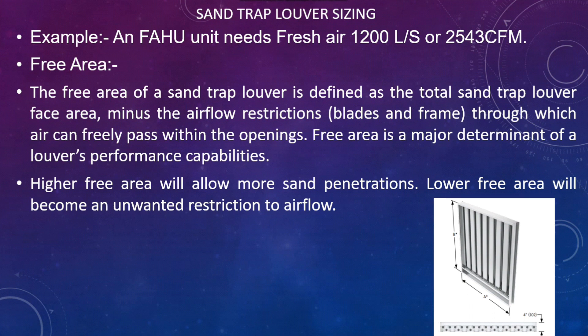The first important thing here is the free area. The free area of the sand trap louver is defined as the total sand trap louver face area — that is A times B as shown in the drawing — minus the blades and frame area. So we need to subtract that from the total area to get the free area. A higher free area will allow more sand penetration, and a lower free area will become an unwanted restriction to airflow.